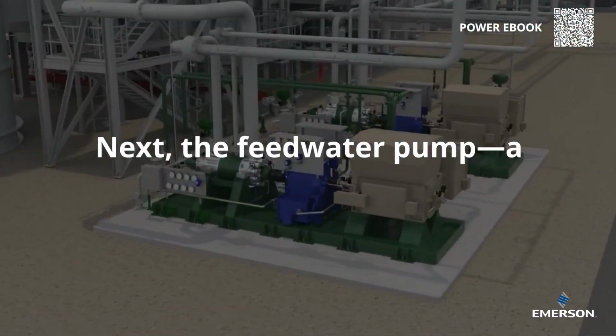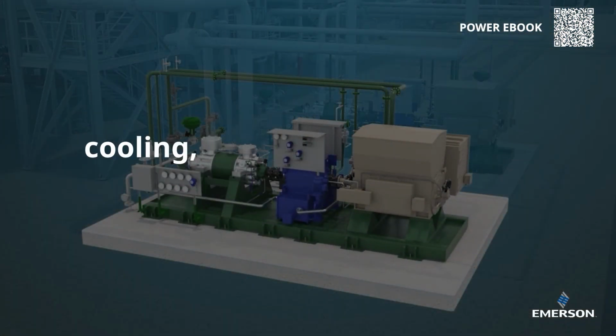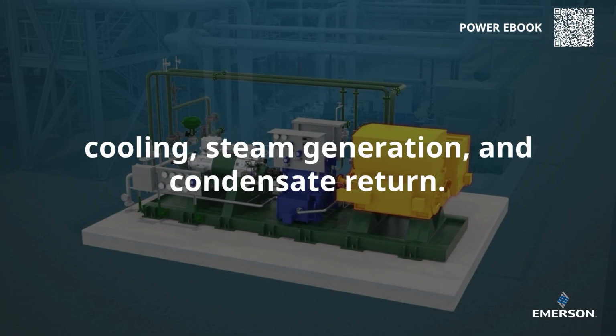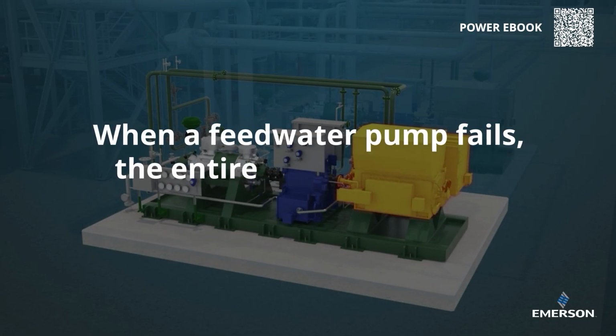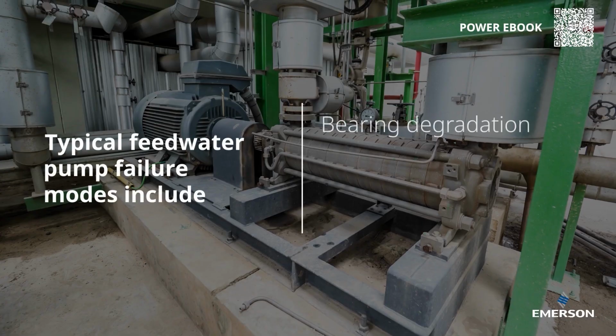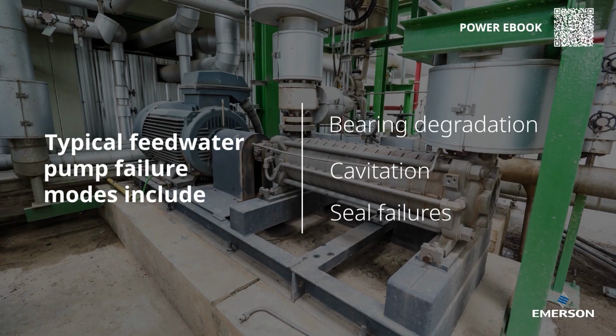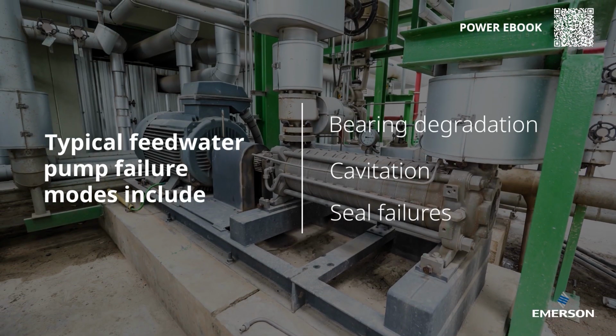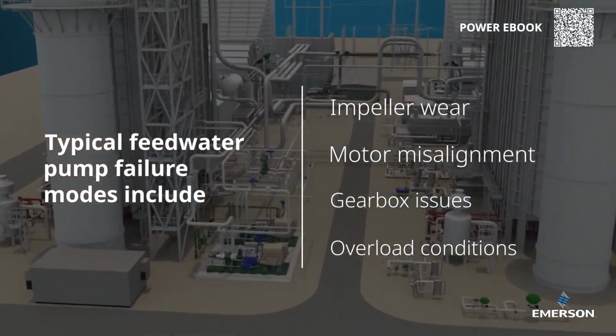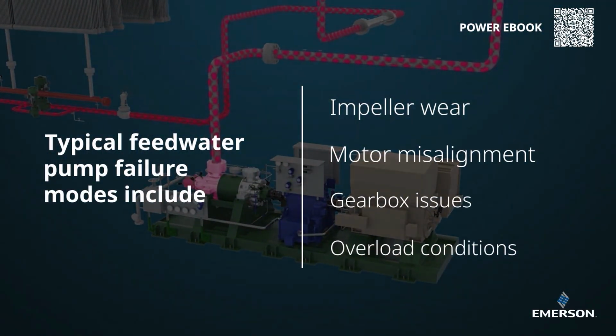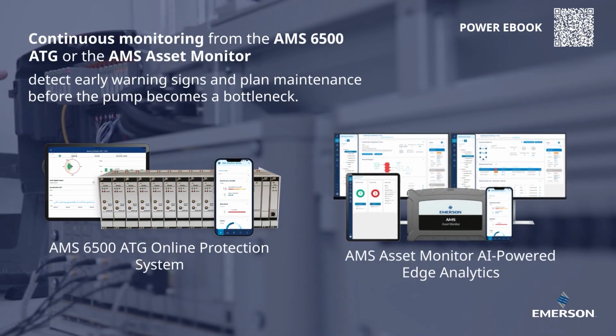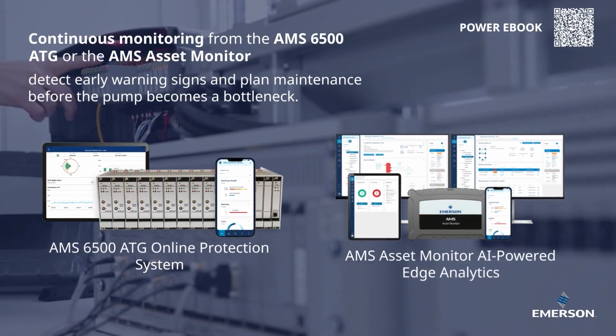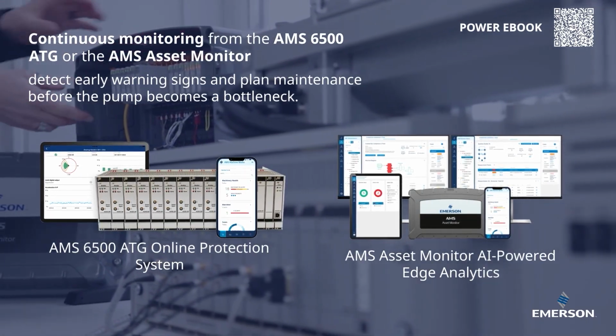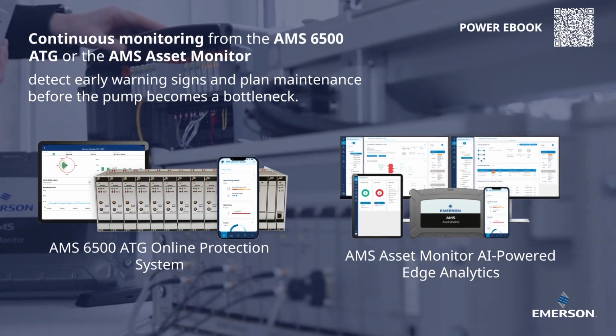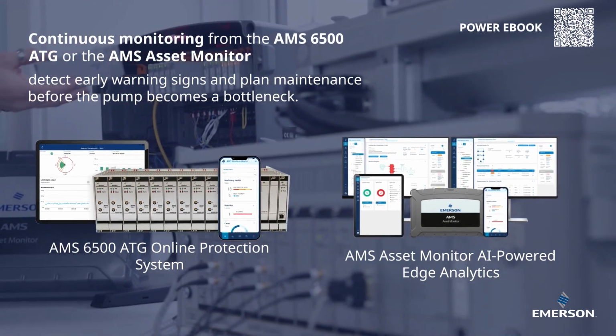Next, the feedwater pump, a workhorse that supports cooling, steam generation, and condensate return. When a feedwater pump fails, the entire steam cycle is at risk. Typical failure modes include bearing degradation, cavitation, seal failures, impeller wear, motor misalignment, gearbox issues, and overload conditions caused by water intake disruptions. With continuous monitoring from the AMS 6500 ATG or the AMS Asset Monitor, operators can detect early warning signs and plan maintenance before the pump becomes a bottleneck.